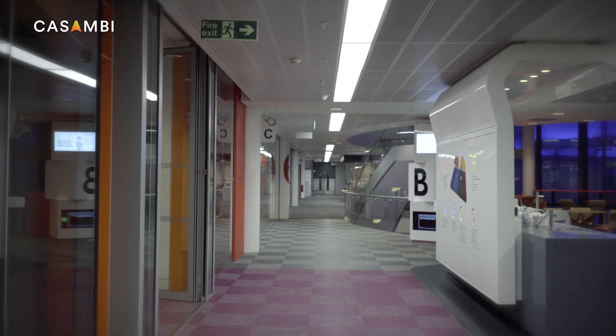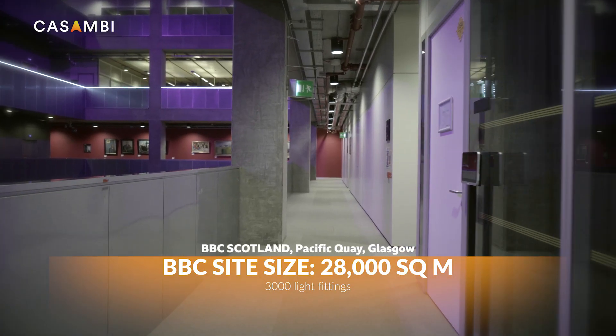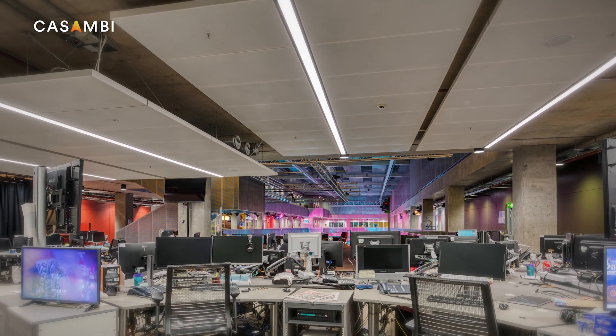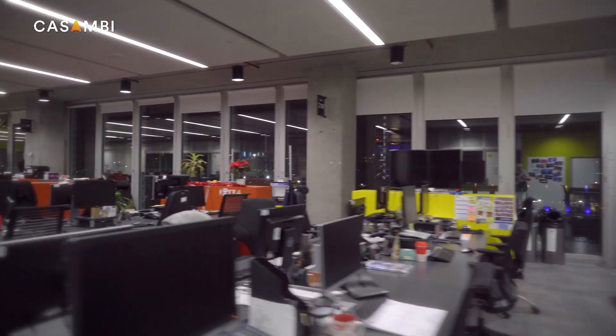The collaboration with WILA was very important in regards to dimming technology — through dimming curves, through the tunable white functionality that was provided. The luminaires installed were part of the WILA range called Cluster: a mixture of 1200x300 and 1500x300 backlit LED luminaires with a microprismatic controller for glare control. The Casambi elements were integrated into the gearboxes on the back of the luminaires, with the aerial exposed, as well as sensors in positions previously used and switches where required.